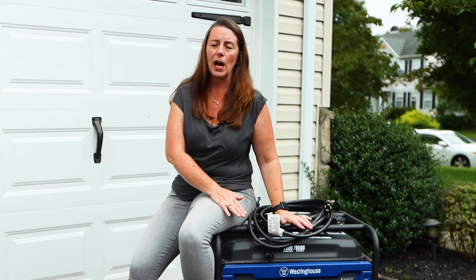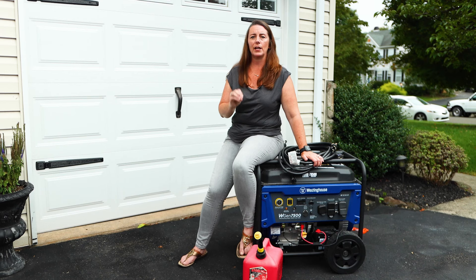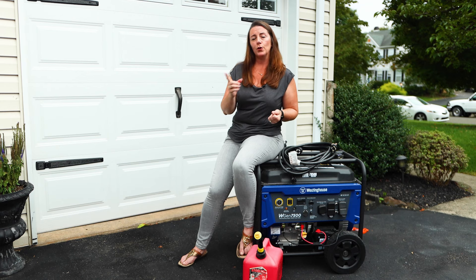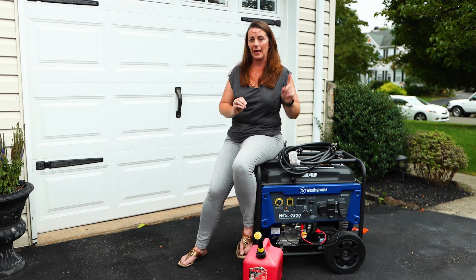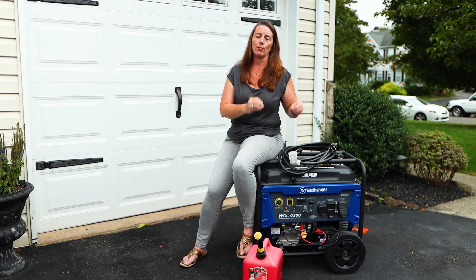In this case, we spent about $800 on a high-powered generator to run most of the home, and about $800 on the electrical work to make sure the house was wired properly and the circuit breaker panel was installed correctly. If you were to hook a generator up to your house and backfeed your circuit breaker without the proper steps, you can actually send electrical current down the power lines and injure or kill one of the linemen. So it's important that you use the 30-amp system properly.